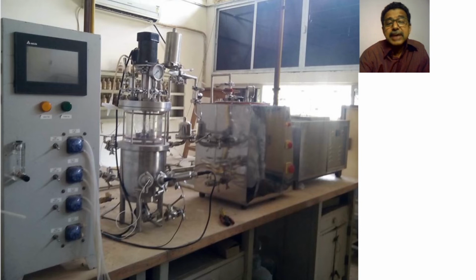Okay, bottom side, it is a jacketed stainless steel vessel, where you find three different probes connected. The first one, the white colored wired probe, is the temperature probe, which detects the temperature, and that detection is given to the control unit, and the control unit will take care of controlling the temperature automatically. We'll see it in the next picture also.